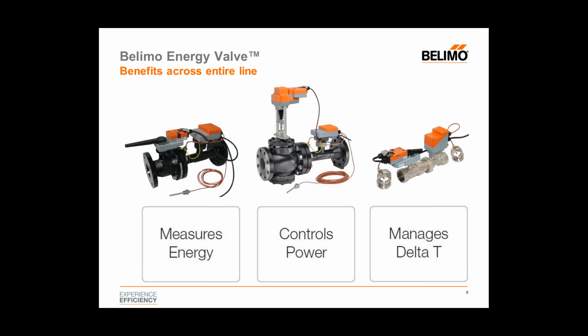It also has the ability to control power. As we talked about before, with that DDC signal correlating directly to a BTU output, now it gives us another way to control the temperature in the space directly to a BTU. So for some critical application environments where the BTU output is absolutely critical to the space, there's now a way to directly correlate that within the space, something that no other product in the marketplace can currently do.